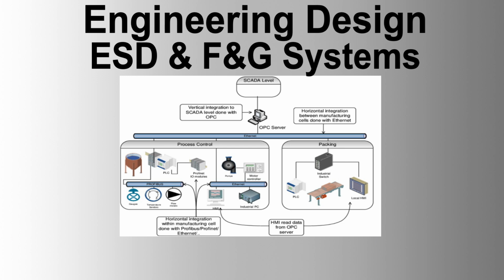System size and capacity. 1. I/O processor modules. Provide I/O processor modules with an additional 20% margin for fully wired installed spares. Ensure system mass memory can hold all system and application software and database with the capacity for future programming and configuration. Supply 24-volt DC power to all field devices from dedicated power supplies with proper sizing for maximum load capacity. Ensure all intrinsic safe I/O channels are equipped with galvanic isolators.